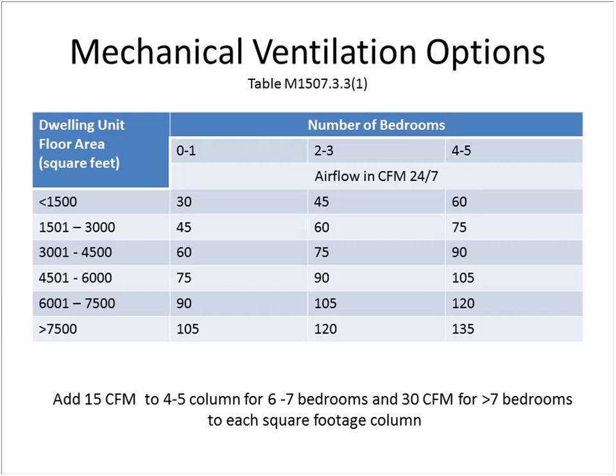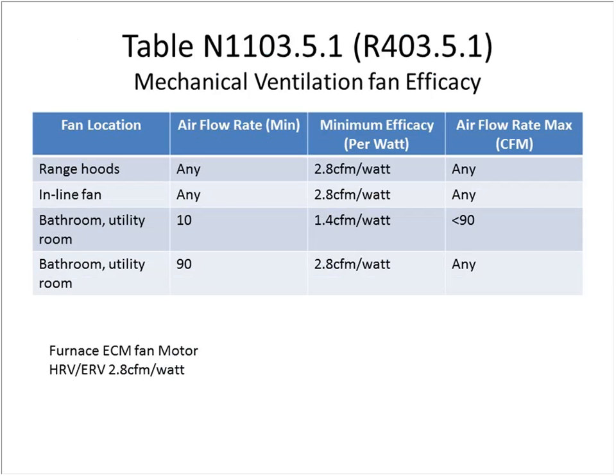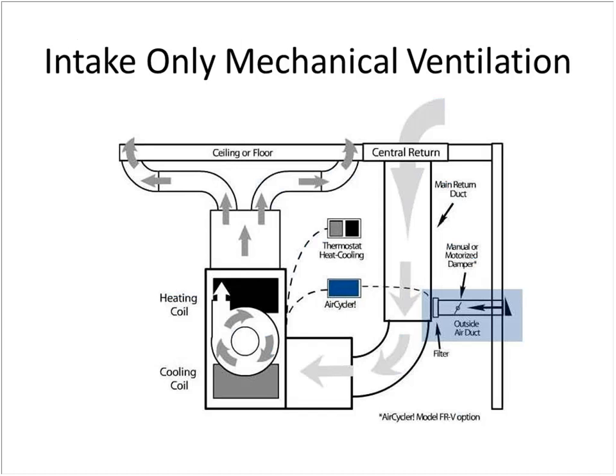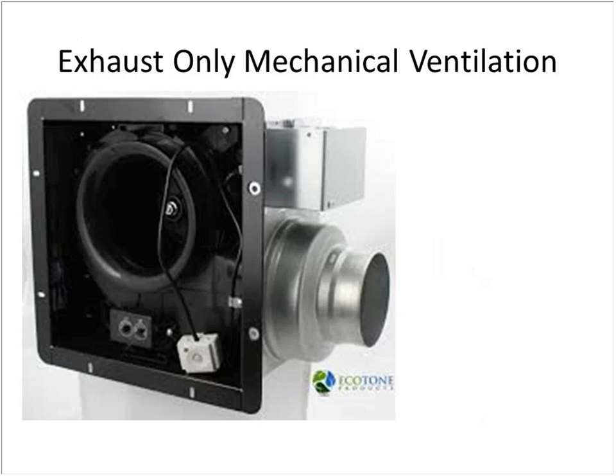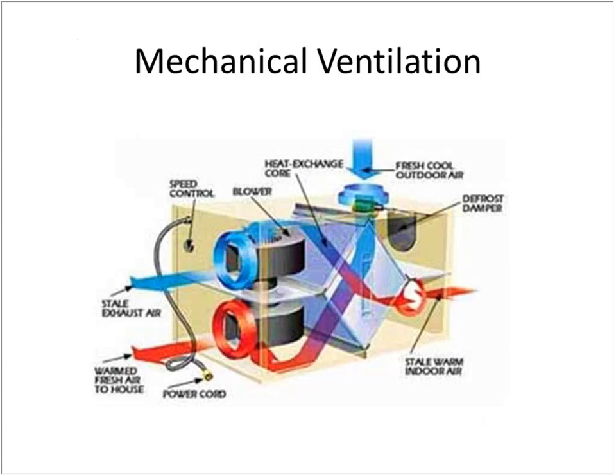And I expect that in the years to come the people that write code will be evaluating ventilation to make sure that we're not over ventilating at too high of a rate, because it impacts comfort and indoor air quality if it's too high as well as if it's too low. But anyway, the chart's available there, and that's what they'll be expecting to see, a system that can provide that type of ventilation. That's the efficacy. This is an intake-only system. Jeff will be covering these. Exhaust-only system, and then mechanical ventilation is ERV.